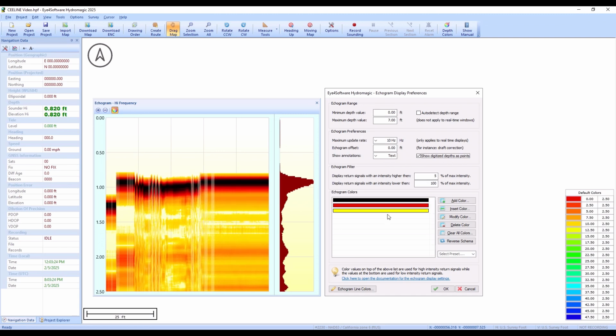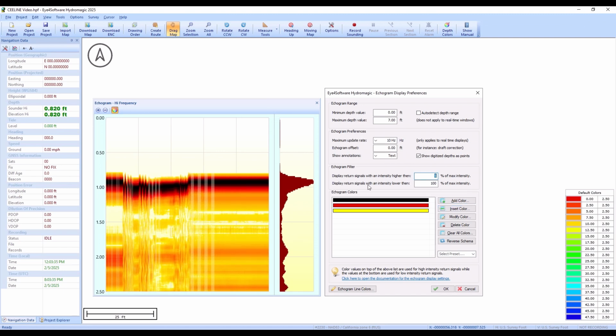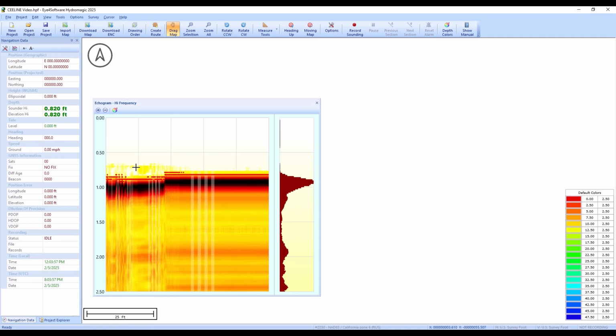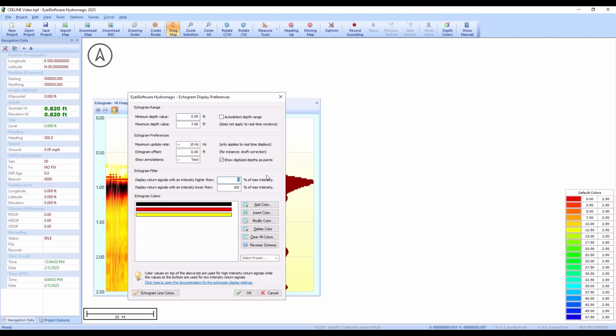These color bands, this black, red, yellow is quite good, so you would be recommended to leave that as it is. And also the percentage of maximum intensity, 5% minimum. It's not going to be reporting any signal back below 5%. That's to remove really low level noise to give you a nice clean image here. But you can change that. But say if we put 1% here, you see a little bit more noise appears. Kind of just makes things a little bit more messy. So it's nice just to keep that at 5.